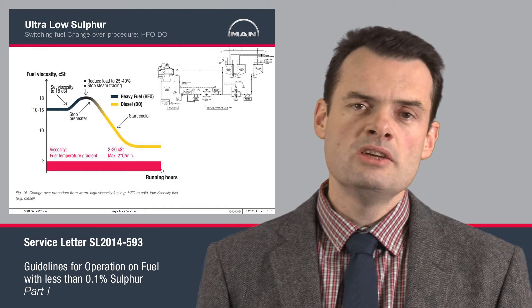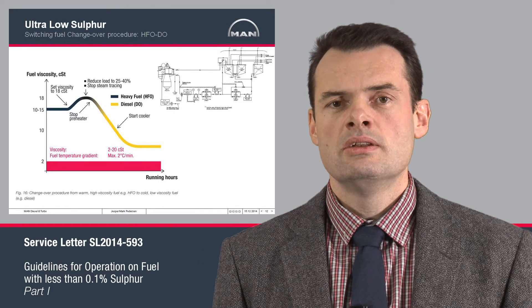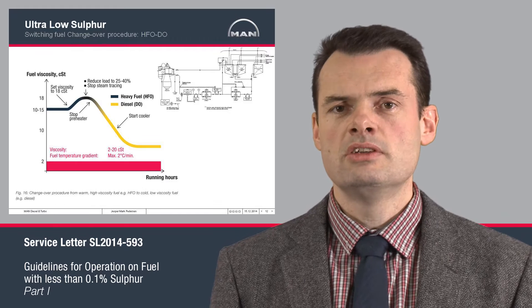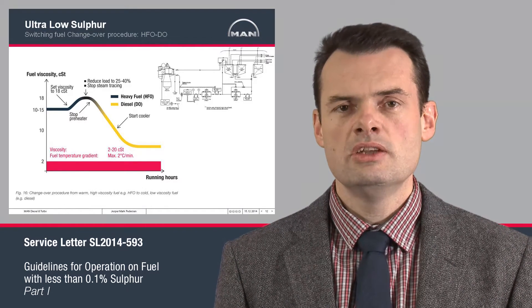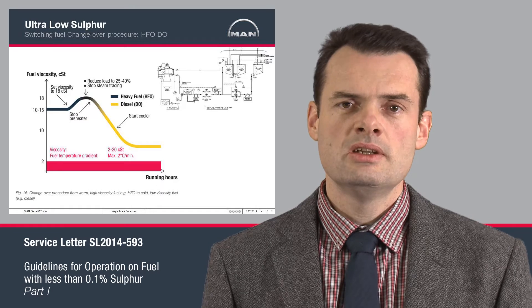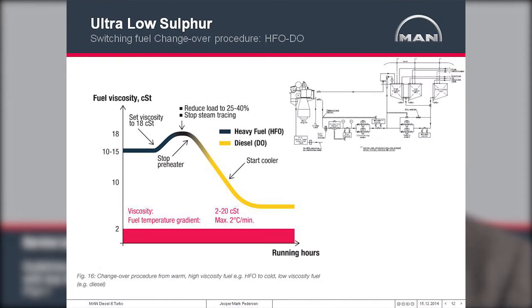Our recommendations for switching between hot heavy fuel oil and relatively colder distillates is to decrease the engine load to 25–40% and then switch the fuel valve. During the switch period, the engine load should be monitored, and very importantly, the viscosity.